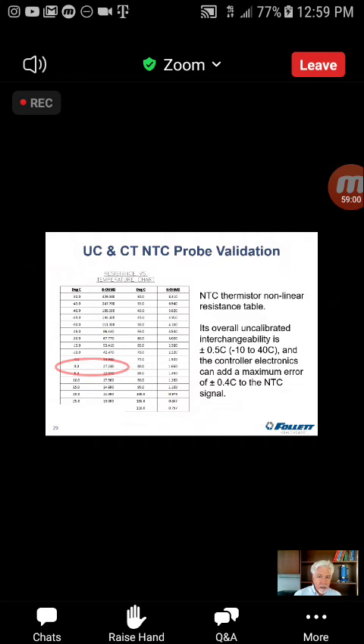So if that probe is showing off spec, we can double check it. We can make sure that it is the probe and not something in the communication harness, something in the connection to the board. We should validate it independently. Now, when you look at the connector where these probes get connected to the board, there is only a very, very small area of conductor available. So if you have probes with very sharp and fine points on the ends of the tips, you can get at that. Most of them don't. The probe that I use, the meter that I use, they are not sharp enough to get to those. So what I do in order to read that, take a small piece of 16 gauge multi-strand wire, strip it and cut individual little strands, and you can insert the strands into where the connector goes onto the pin of the board, and then measure across the two pieces of copper.